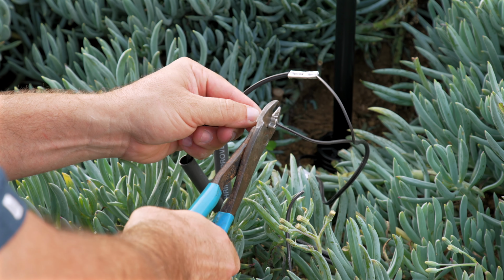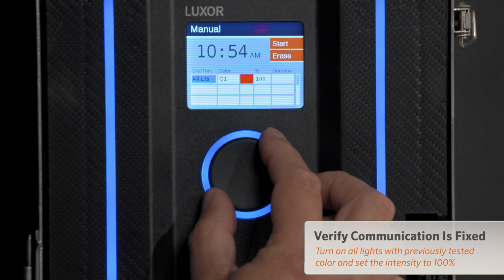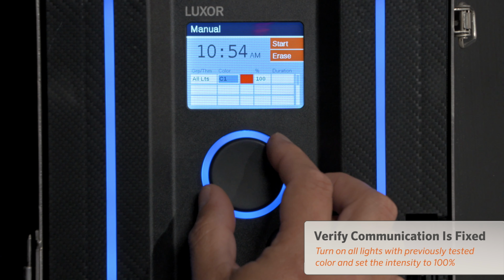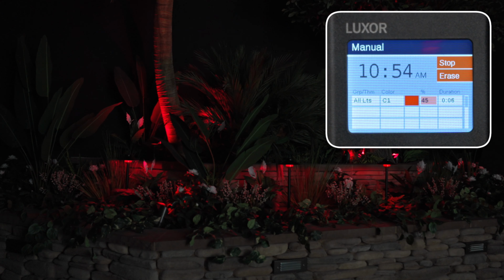To verify communication has been fixed, go to Manual, select All Lights, select the same color that you tested with the first time. Select a time. And press Start. Make sure that the fixtures are turning on to the correct color. That verifies that color communication is operating correctly. Go back to Manual and adjust the intensity to make sure that the fixtures are still communicating. The intensity should change out in the field to match. Once that is confirmed, raise the intensity back to 100%. As a final verification, change the fixture color again. This shows the wiring connection has been fixed.